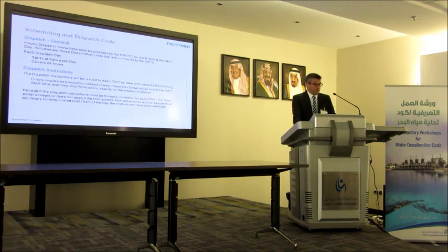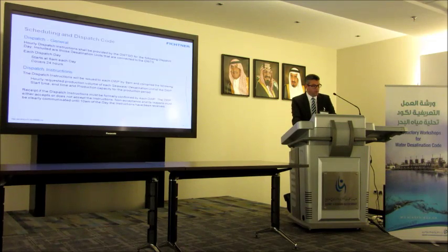The dispatch instructions shall be provided by the transmission system operator for the dispatch day, which is the day tomorrow from 6 to 6. And these dispatch instructions include all these desalination units which are connected to the transmission system. The dispatch instruction shall be issued also at 9 a.m. of each day, comprising the hourly requested production volume of each unit and the start time and end time production capacity of such production period.